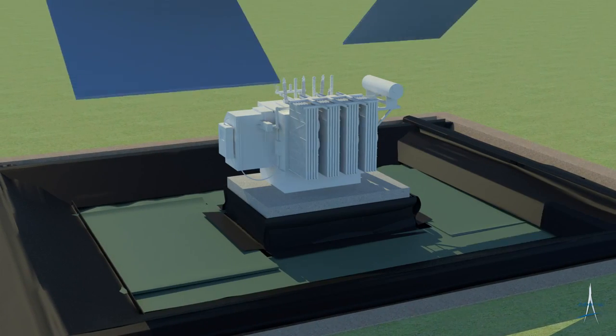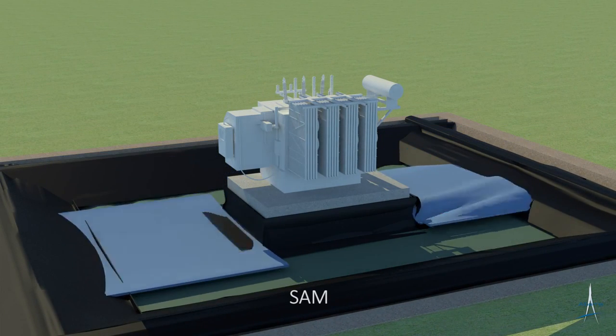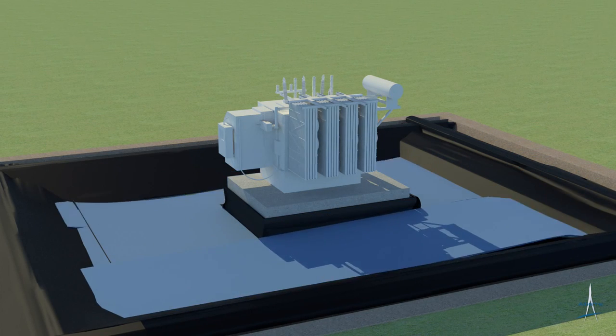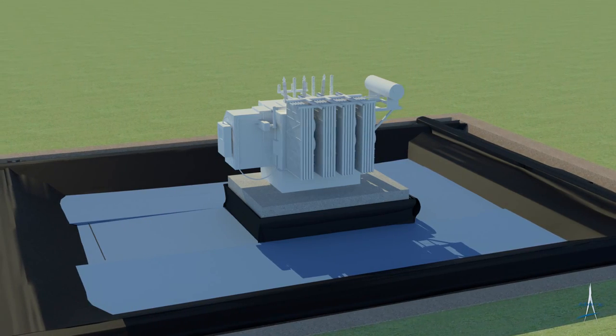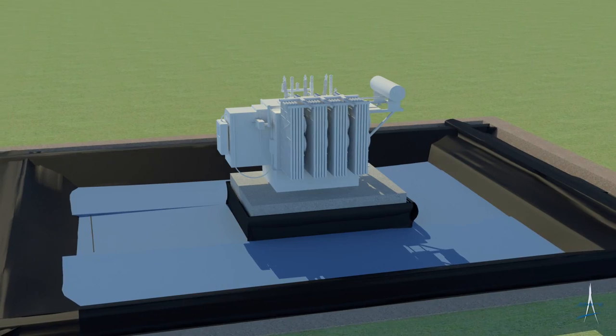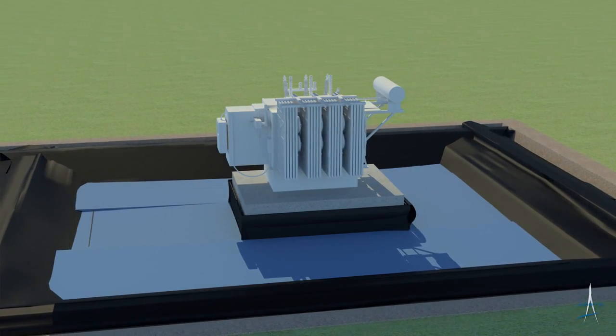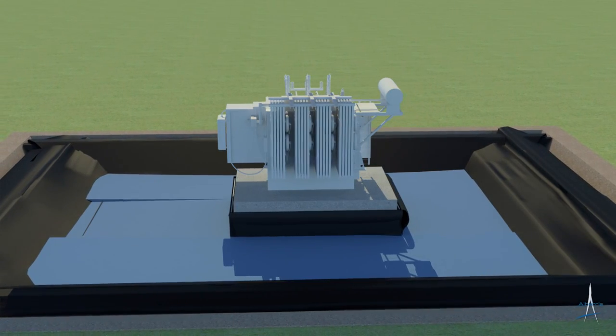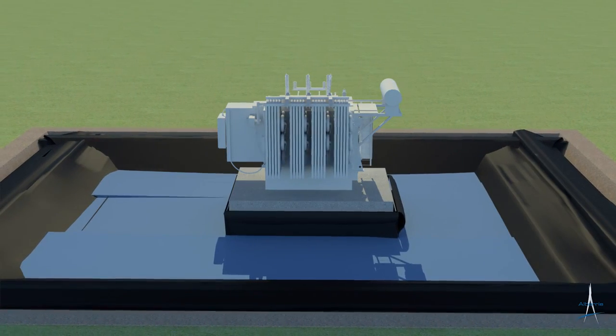Special geotextile SAM, also known as the absorbent layer, is now installed throughout the containment area. SAM is a unique geotextile loaded with a proprietary blend of polymer. It has an exceptional absorption capability per square inch and it serves to extend the service life of the containment by protecting the oil mat from small accidental leaks.